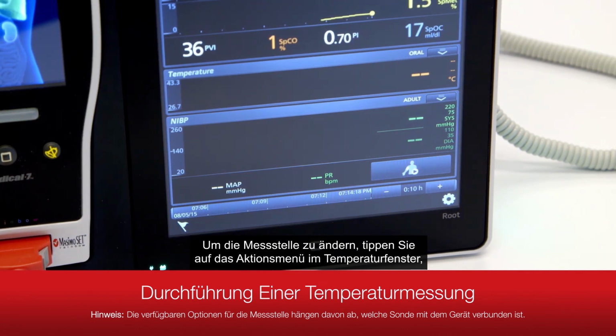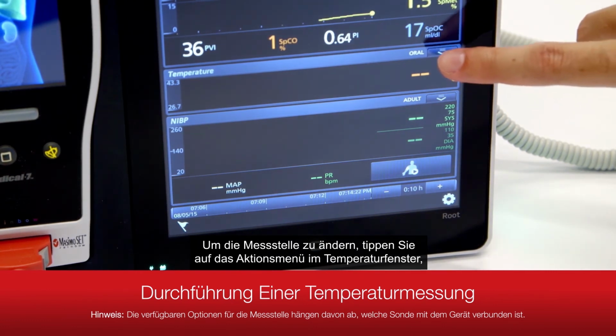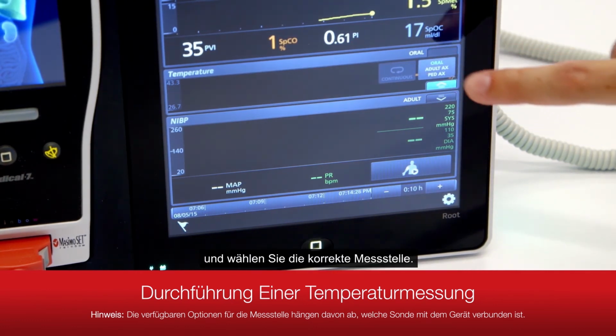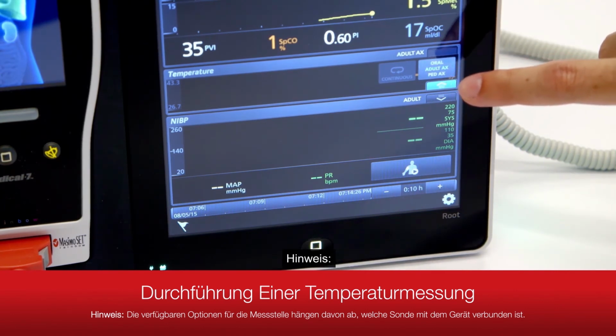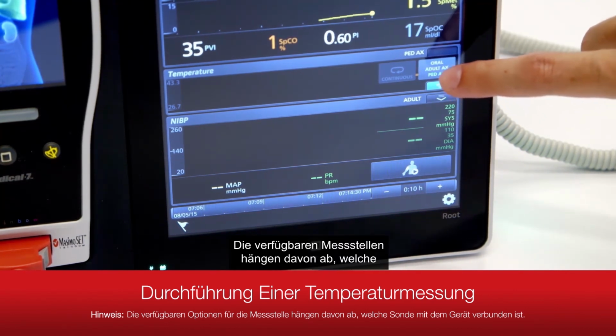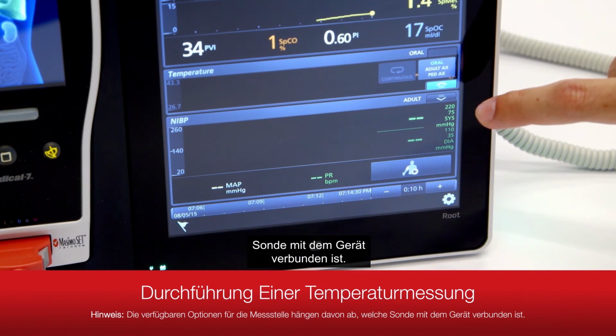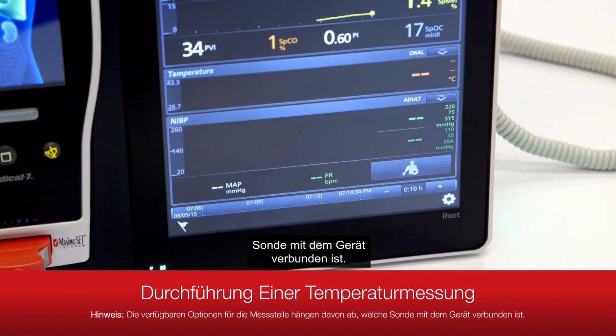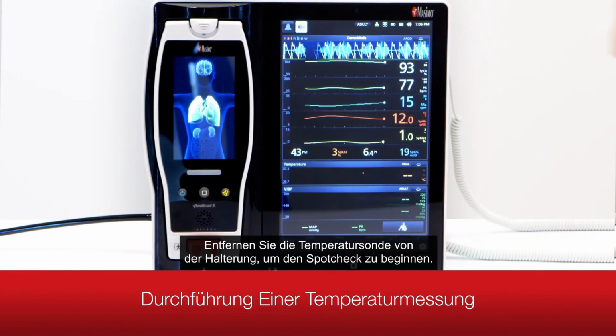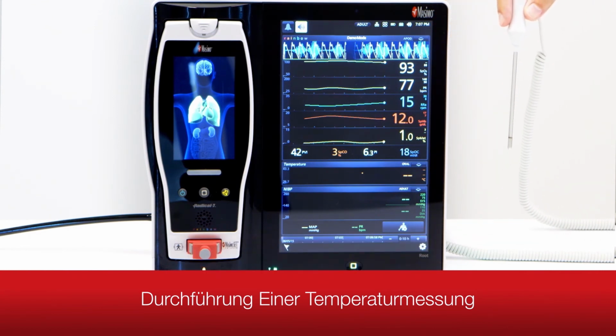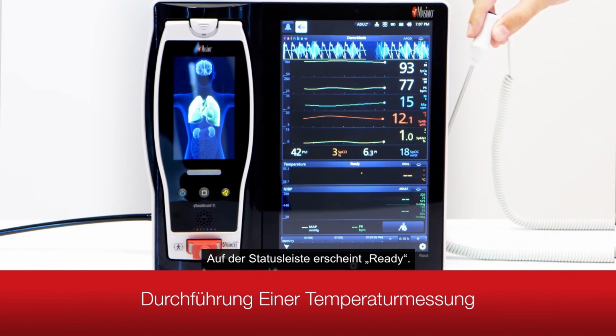To change measurement site, touch the Action menu in the Temperature window. Select the correct measurement site. Note: the available measurement site options are dictated by whichever probe is connected to the device. Remove the temperature probe from the probe well to initiate spot check. Ready will appear in the status bar.